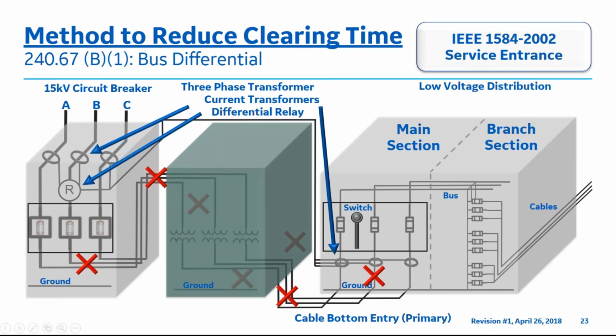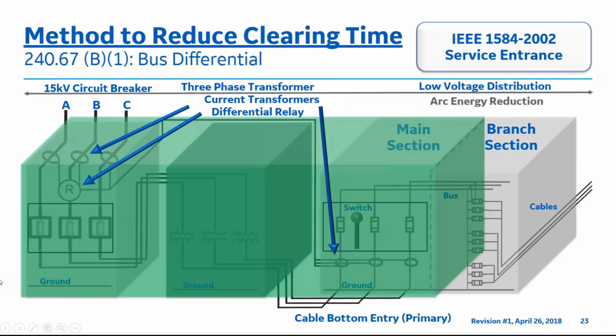The purpose of this slide is to provide both line and load side arc energy reduction for this area. The protective relay would not pick up any arcing faults downstream of the CTs, which would be located physically above the CTs in the main section. Please refer to 240.67b and b2 for the arc energy reduction examples provided in this presentation.